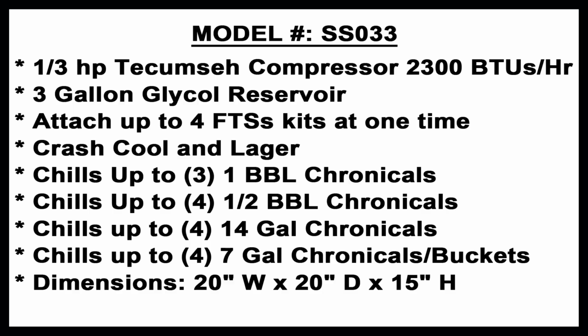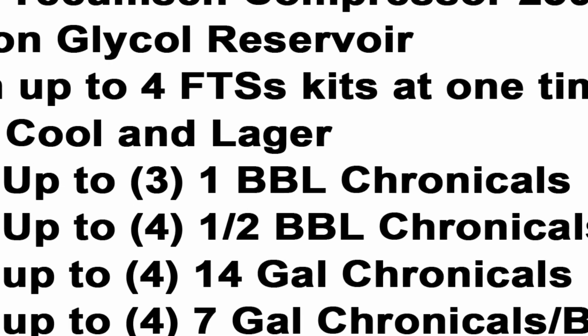This unit did that for me. I was able to run 3 fermenters and a bright tank. Now, if you look on their website, their specs say you can only do 3 one-barrel tanks. But here's the reality: typically during fermentation, the chiller's not running continuously, it only kicks on to maintain fermentation temperature. So as long as you don't have multiple tanks crashing at the same time and you time it out correctly, you can actually have more tanks on it. That worked out really well for me.